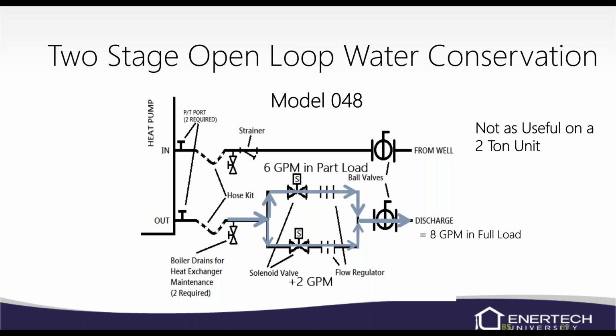Now we get into a 2-ton or less, it's probably just going to be best just to put one solenoid valve and one flow restrictor in and be done with it. We don't have 1 GPM flow restrictors. We only have 2 through 10, I think, or somewhere in there. I know 2 is the lowest. So we really can't do a 1 GPM flow regulator.